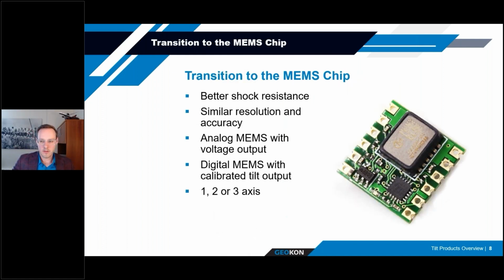So, moving on to the MEMS chips that you will typically find in most modern tilt products. Again, these are MEMS accelerometers, but we're not using them to measure acceleration. There's a whole product line of MEMS chips that are used to measure static tilt that are specifically designed for that application. They offer extreme resistance to shock, upwards of, in some cases, 2,000 to 5,000 G. You can get very high resolution, precision, and accuracy, in particular with subsequent in-house calibration.